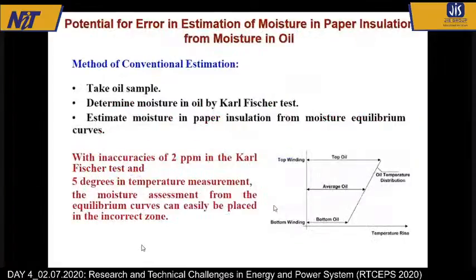Then how can we get the paper moisture content? One way is to find out through the curve that I have shown you: if I know the oil value, I can get the paper value. But then there is some problem here. What is that problem? These curves are temperature dependent. Now, typically, if you look at the winding temperature and the top oil, they don't have the same temperature. So which temperature should I take? Generally, if you go and see the thermometers, there will be two thermometers. We call them top oil temperature and bottom oil temperature. We take these two readings.